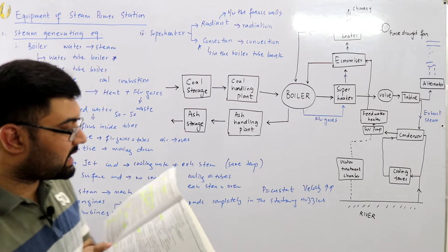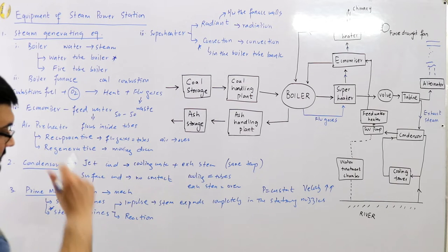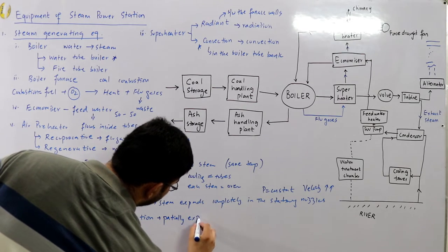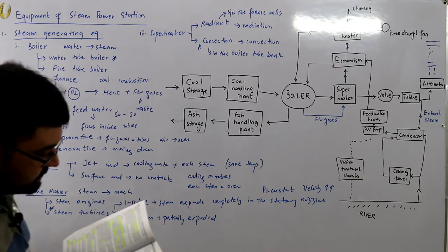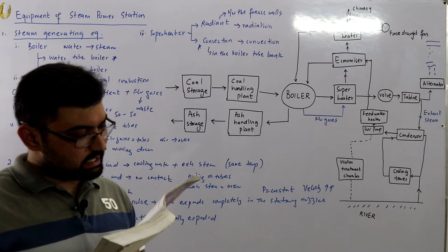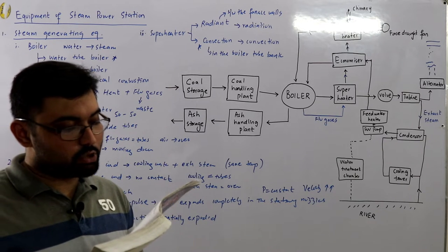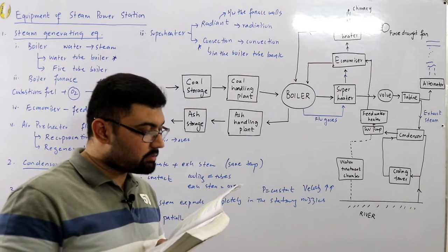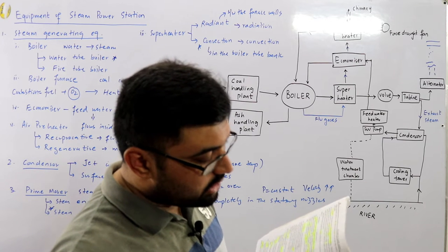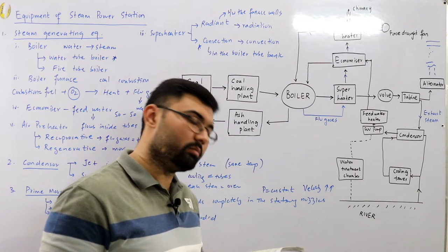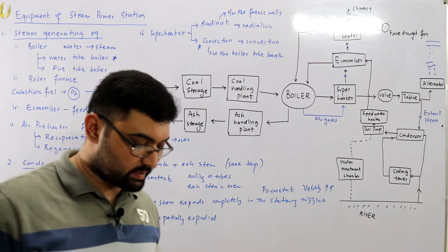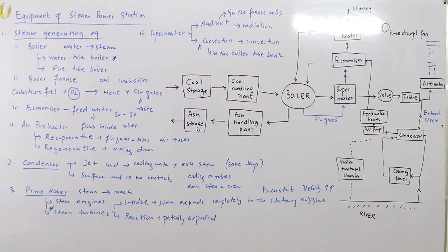In the reaction turbine, the steam is partially expanded in the stationary nozzles. The remaining expansion takes place during its flow over the moving blades. The result is that the momentum of the steam causes a reaction force on the moving blades which sets the rotor in motion. So in the impulse turbine steam expands completely, whereas in the reaction turbine it expands only partially.